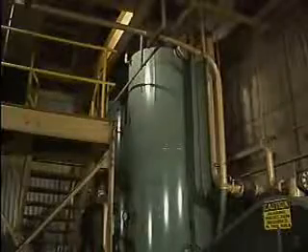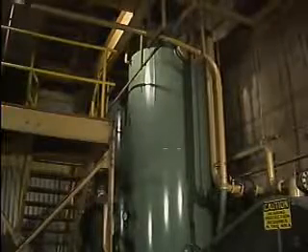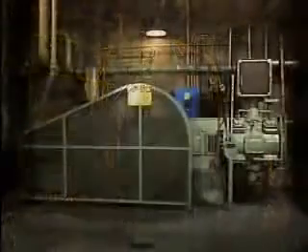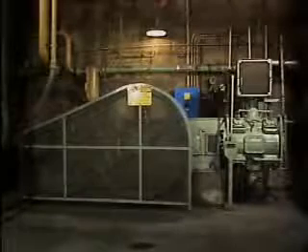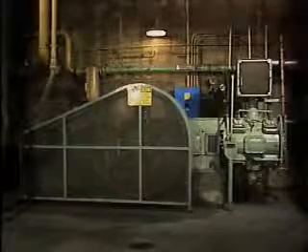Compressed gas that is clean and dry is usually stored until it is needed in the facility. Typically, containers called receivers are used for this purpose. Receivers are large tanks that store compressed gas so that compressors don't have to operate continuously. In most facilities, the demand for compressed air and other gases varies greatly, and the pressure in the compressed gas system can vary with demand.